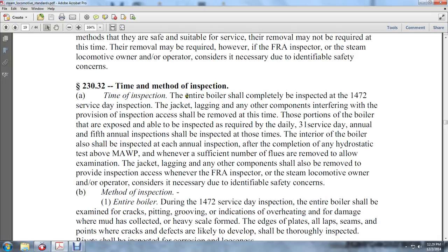Time and method of inspection: The entire boiler is to be completely inspected during the 1472 service day inspection. Jacket lagging and other components interfering with inspection access should be removed at this time so that the portion of the boiler is exposed and able to be inspected. For the annual inspection, the interior of the boiler shall be inspected and a hydrostatic test at the maximum allowable working pressure (MAWP) conducted, with a sufficient number of flues removed to allow examination.